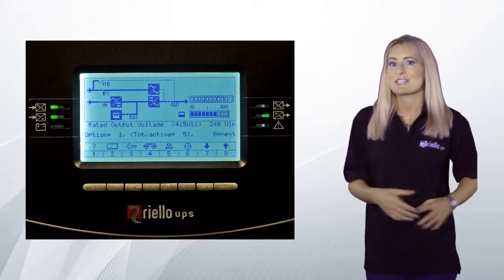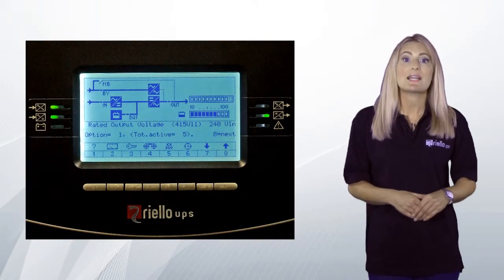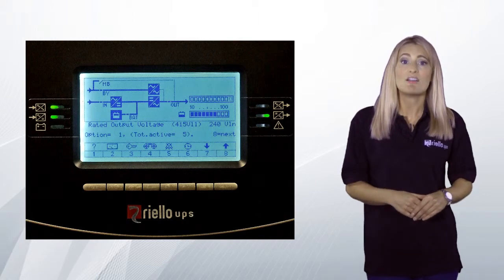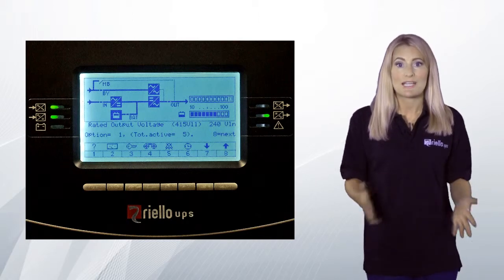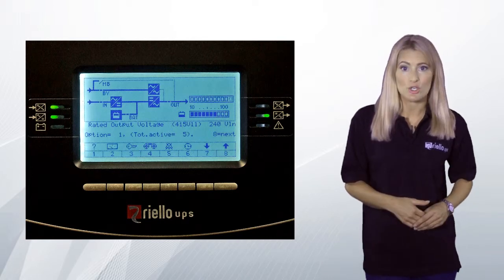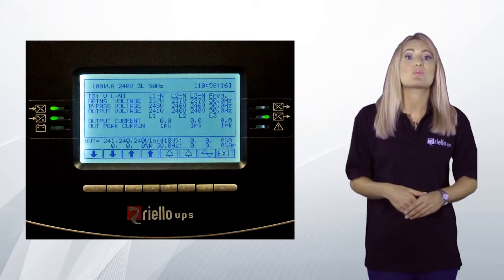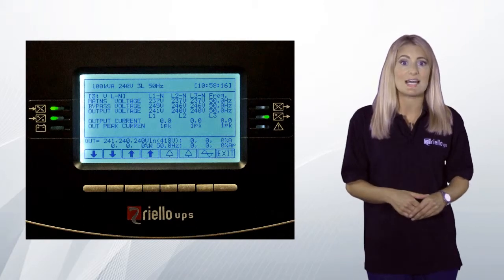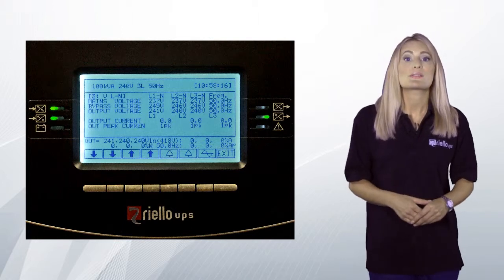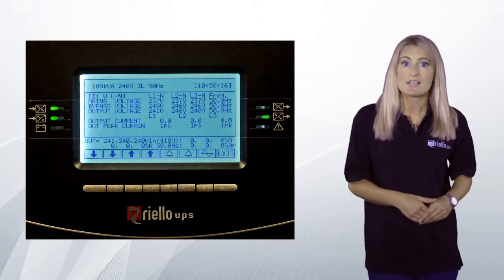From the main menu, press button 7 followed by button 4 to display the active user options that are currently configured on the UPS. Press buttons 7 and 8 to scroll through the configured options. From the main menu, press button 2 followed by button 7 to display a summary of all current system AC and DC voltages. The rectifier supply, bypass supply and system output voltages are all shown as phase-to-phase values. From the previous screen, pressing button 1 or 2 will display the above voltages as a phase-to-neutral value. The output RMS and peak currents are also displayed.